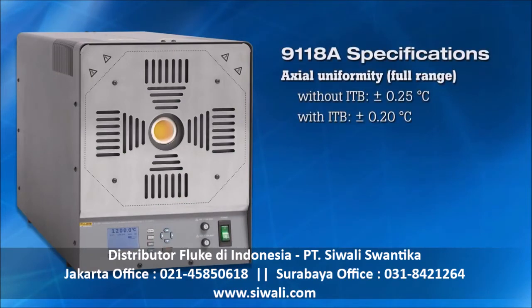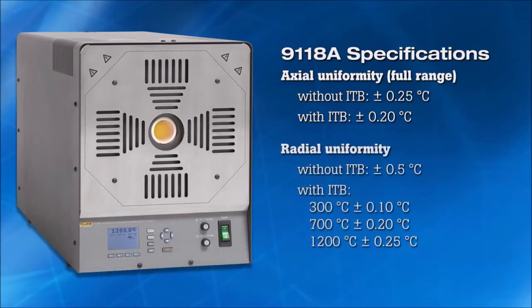The 9118A without the isothermal block has an axial temperature uniformity of 0.25 degrees Celsius. With the isothermal block, axial uniformity improves to 0.2 degrees Celsius. Radial, or hole-to-hole uniformity, is 0.5 degrees Celsius without the isothermal block. With the block, radial uniformity improves to 0.25 degrees Celsius or better. No other calibration furnace in its class comes close to this level of performance for both modes of operation.